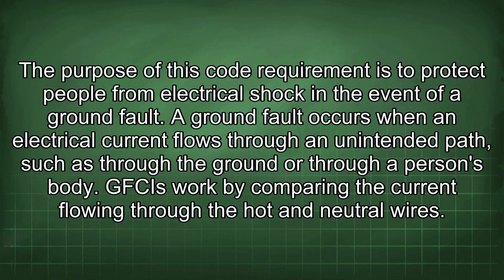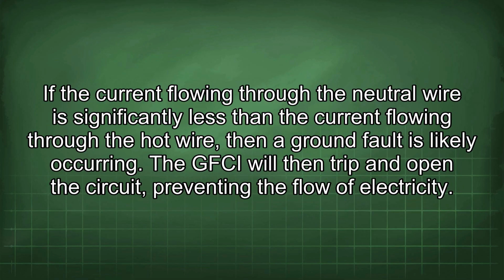GFCIs work by comparing the current flowing through the hot and neutral wires. If the current flowing through the neutral wire is significantly less than the current flowing through the hot wire, then a ground fault is likely occurring. The GFCI will then trip and open the circuit, preventing the flow of electricity.